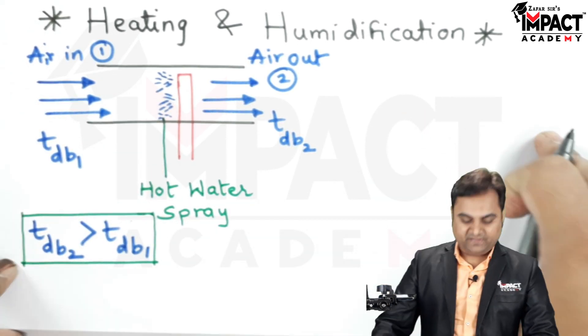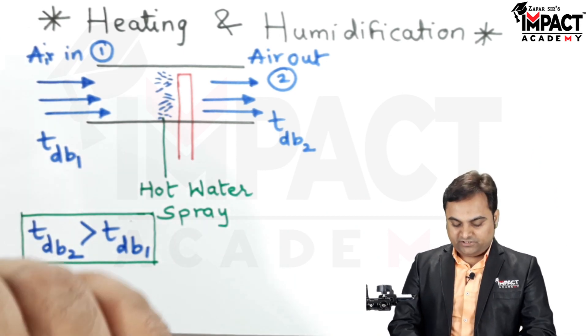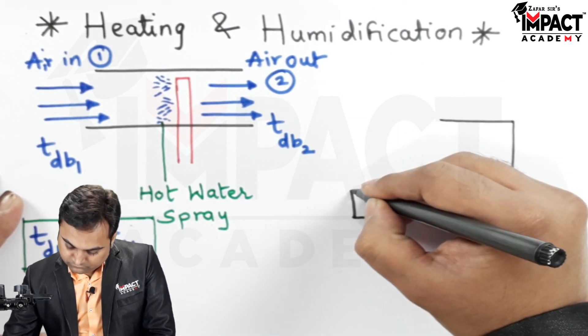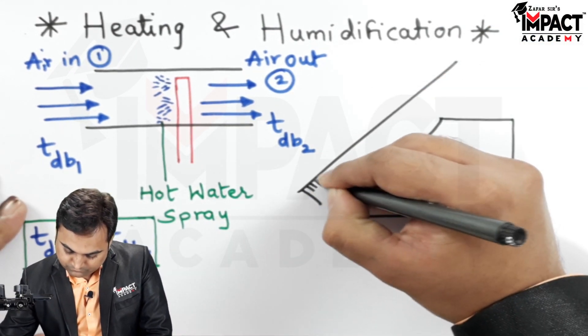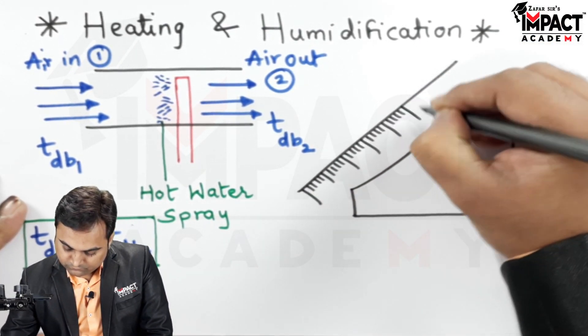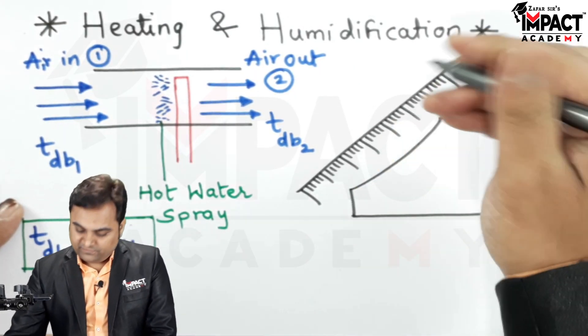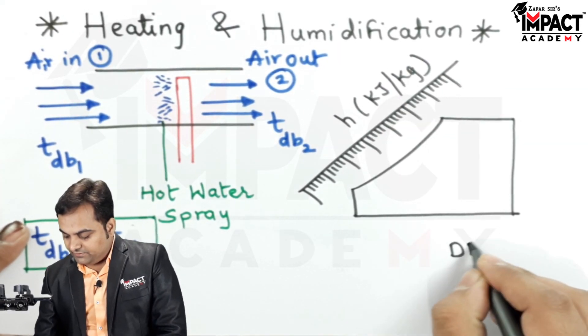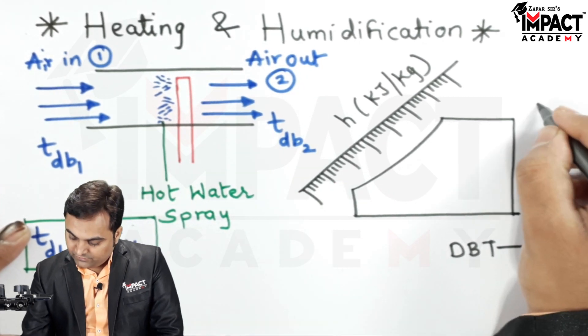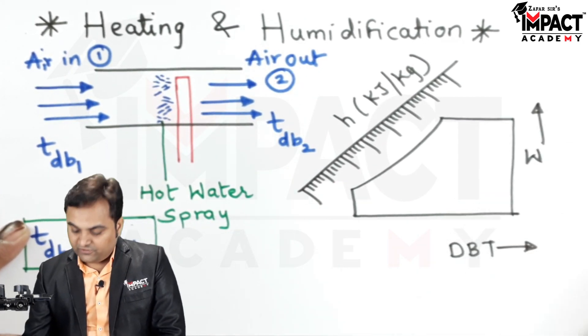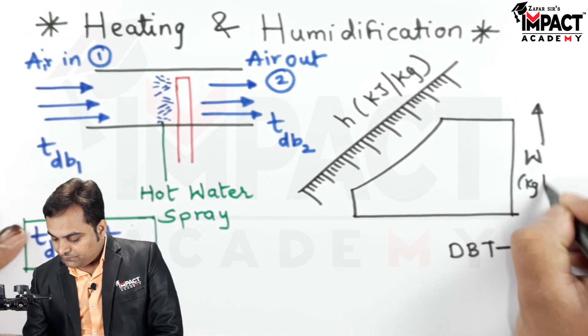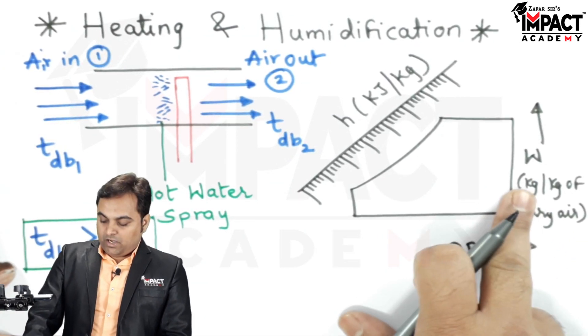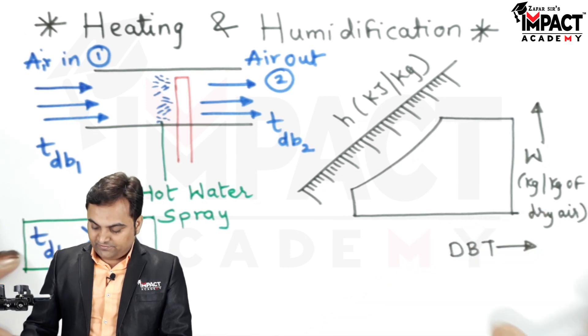I'll now plot this process onto the psychrometric chart. The diagonal scale indicates specific enthalpy in kilojoules per kg, the horizontal axis indicates dry bulb temperature, and the vertical axis indicates specific humidity in kg per kg of dry air — meaning how many kg of moisture or water vapor are present in 1 kg of dry air.